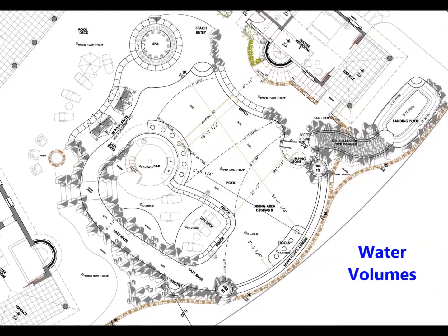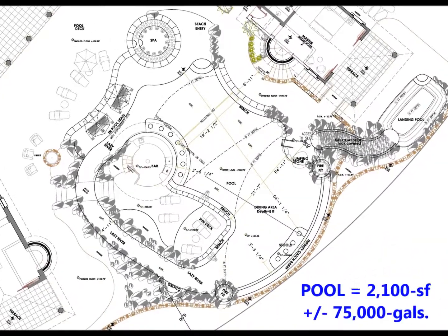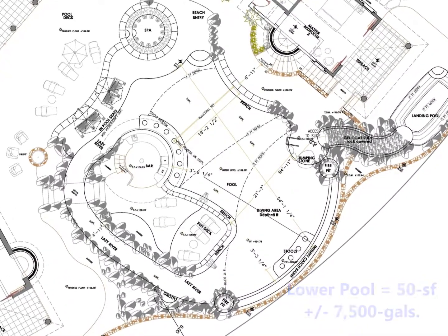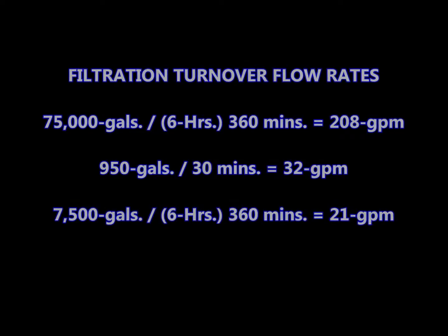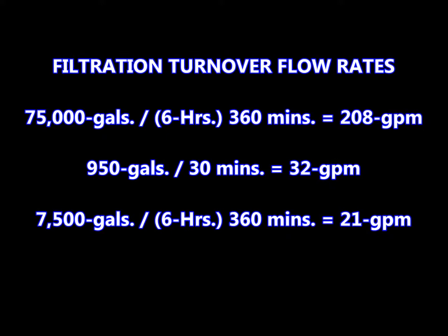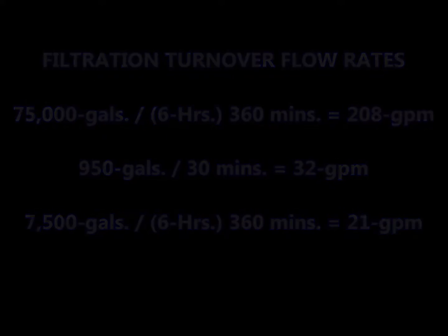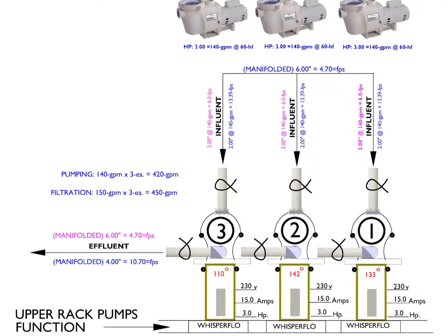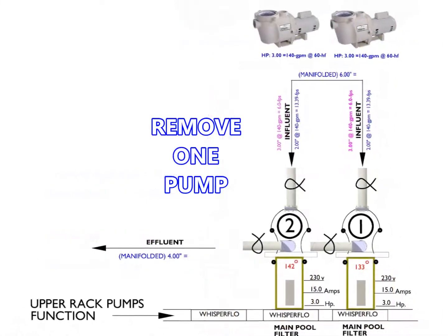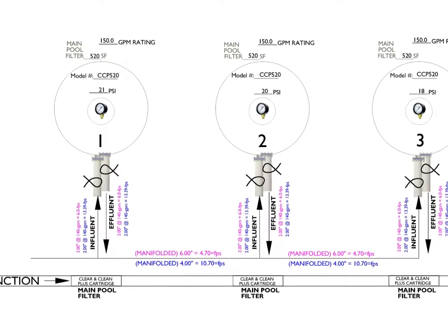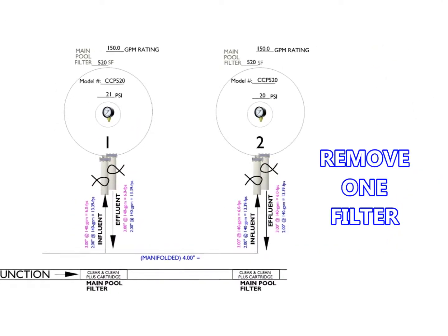In considering improvements, I started with the water volumes for each vessel. The pool volume is estimated at 75,000 gallons, the spa at 950 gallons, and the lower pool at 7,500 gallons. The vessel volumes are converted into the time span turnover rate required for commercial swimming pool standards. Based on these findings, it is my opinion that the electrical energy load of 45 amps currently consumed in driving the three pump motors for the main pool's filtration function could be reduced by one pump and one filter.